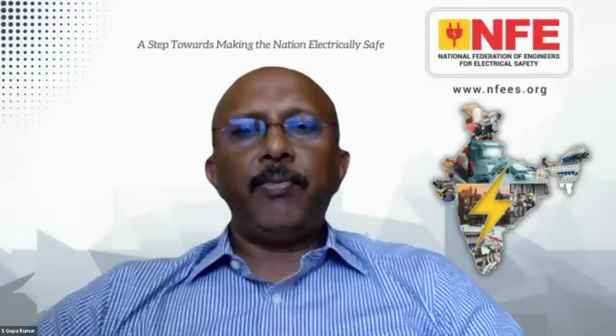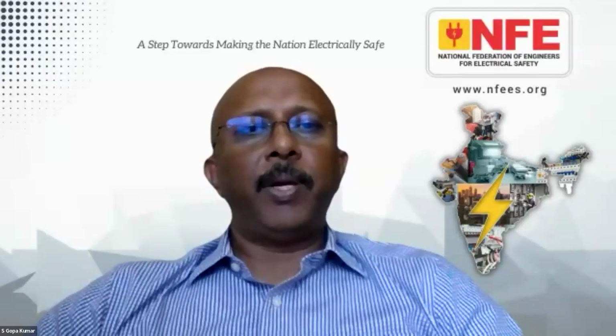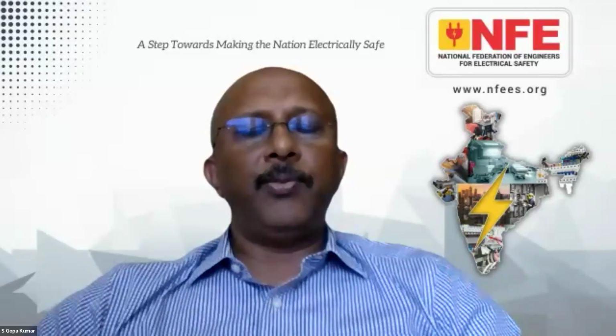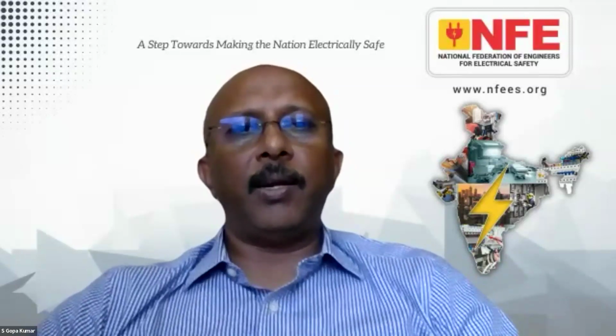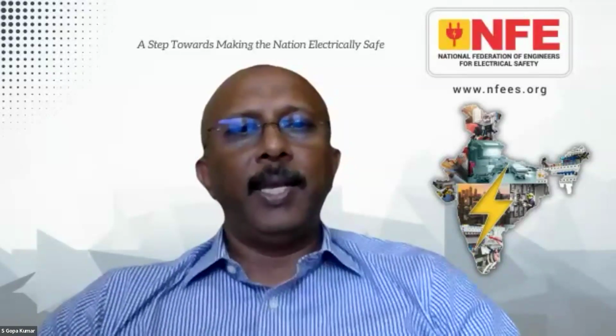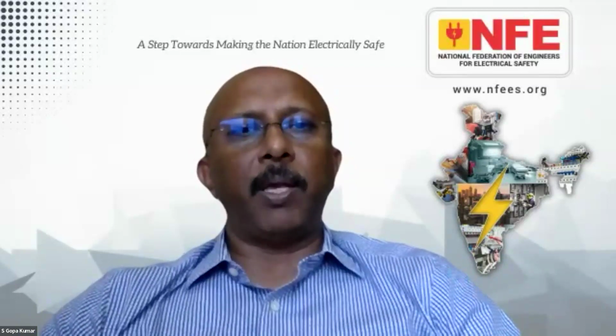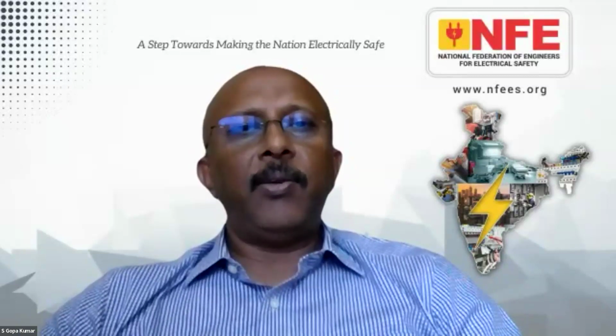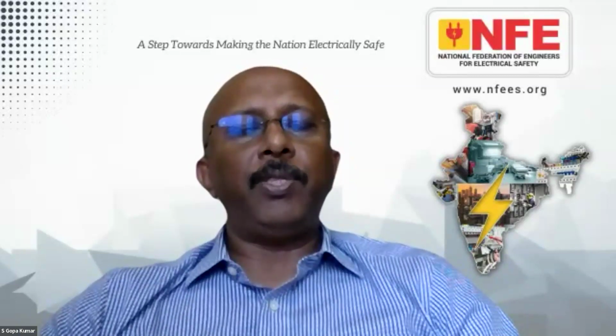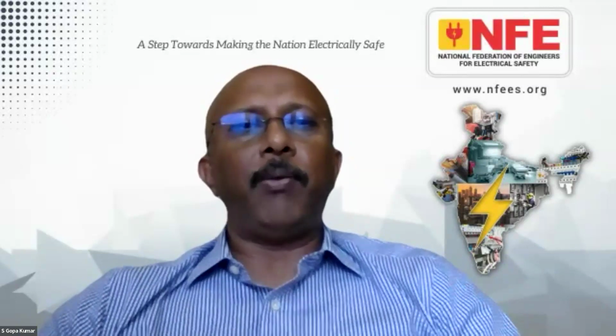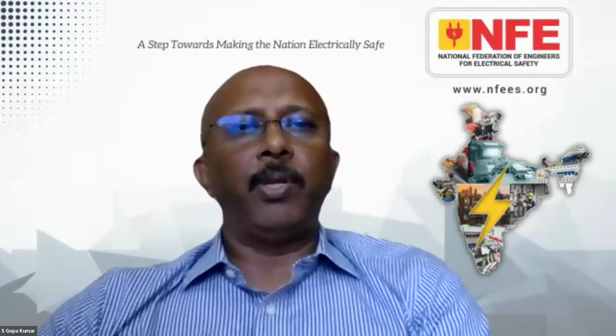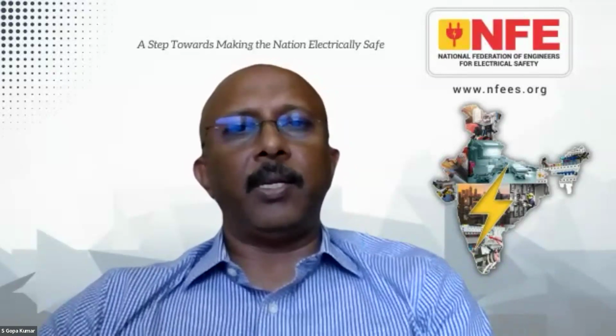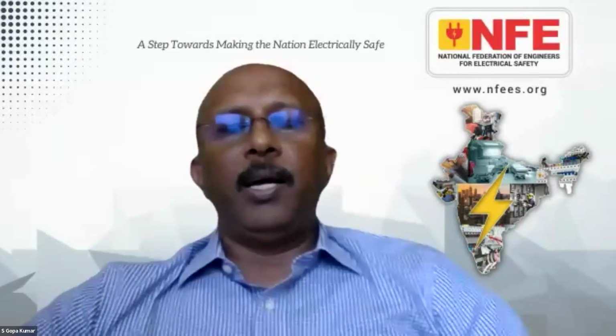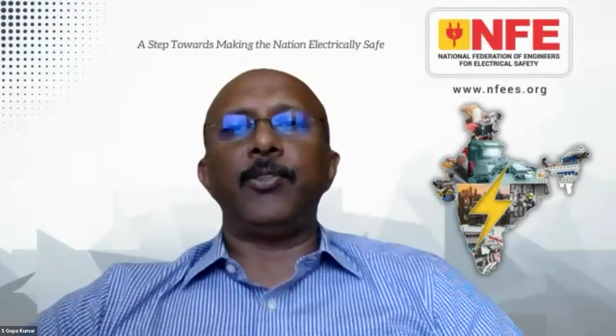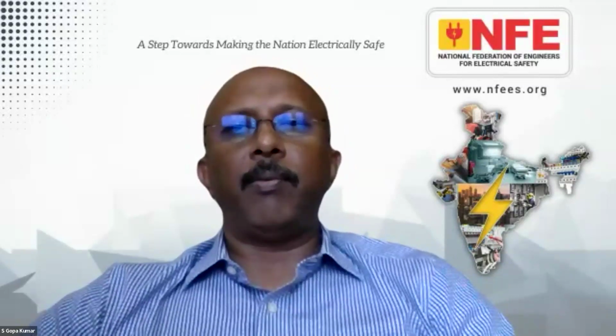Yeah. So do you want to add any more points on this? In case of an ELCB, of course, the calculation is a little bit different, but you have to test. What is written in the standard is the efficiency of automatic disconnection of supply. So first you have to find out the type of protective device which is used for the disconnection, and that particular device should trip. If it's an ELCB, of course, the ELCB has to be tested. Sorry, not ELCB, RCD. The RCD has to be tested.